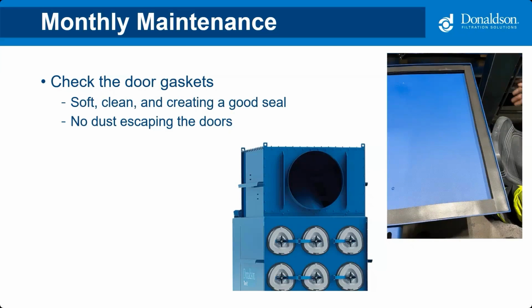The picture on the bottom is a cartridge collector. On those white tri-oval covers, that's the door that you open to actually access and change the filters. Every one of those doors has a black rubber gasket around them. You can kind of see them in the picture. Similarly, you want to make sure they're in good condition, they're soft and pliable, they're not dry cracking or anything like that, and you're not seeing any dust leakage around them, fundamentally.